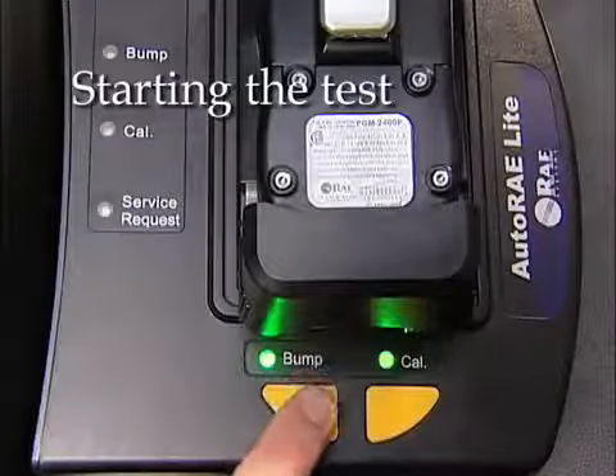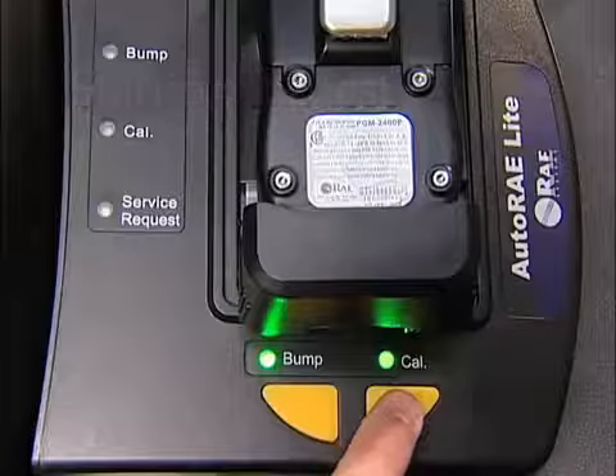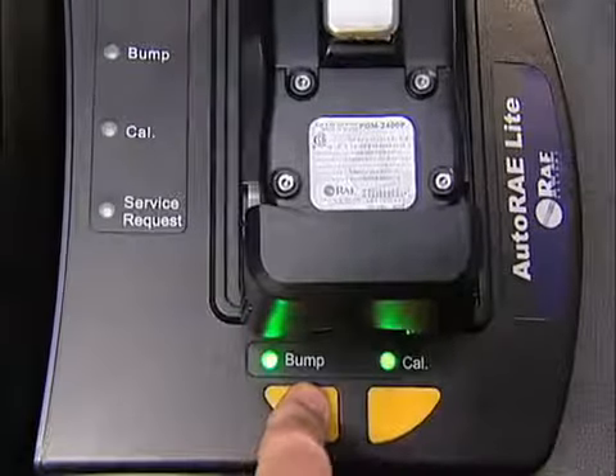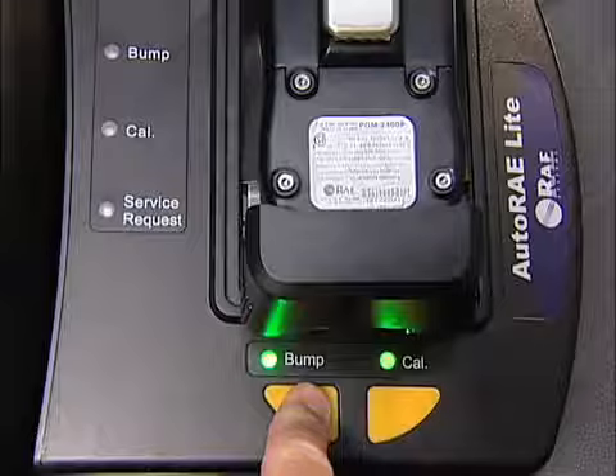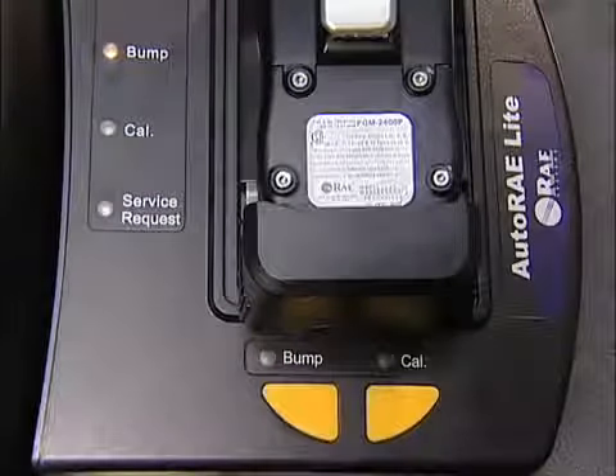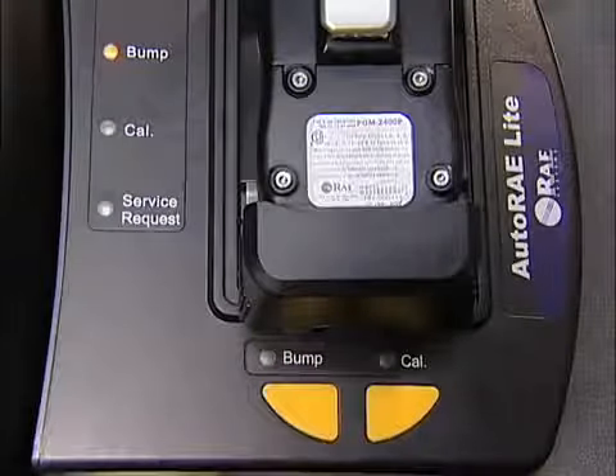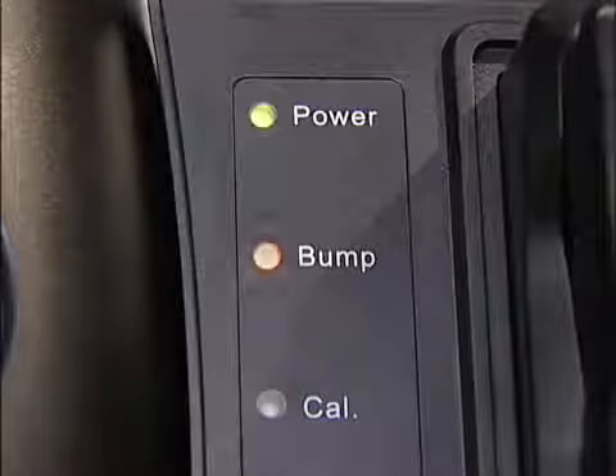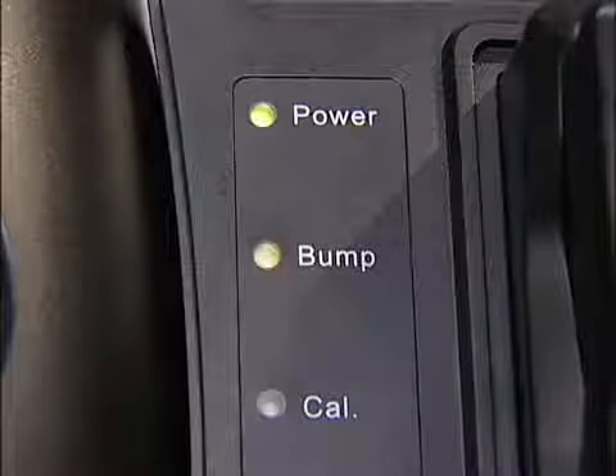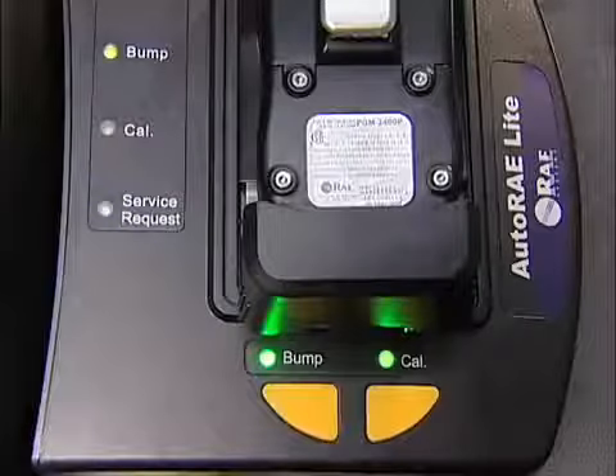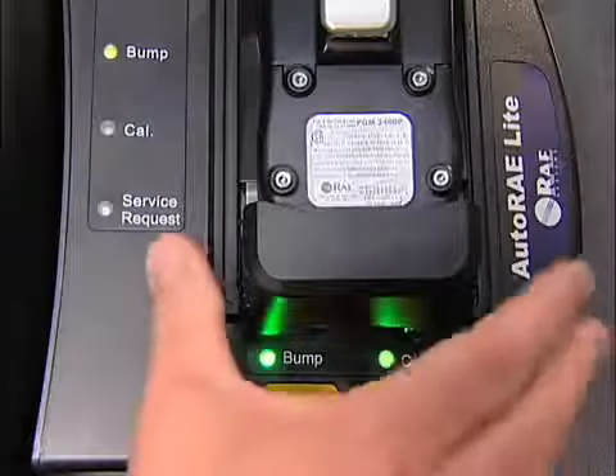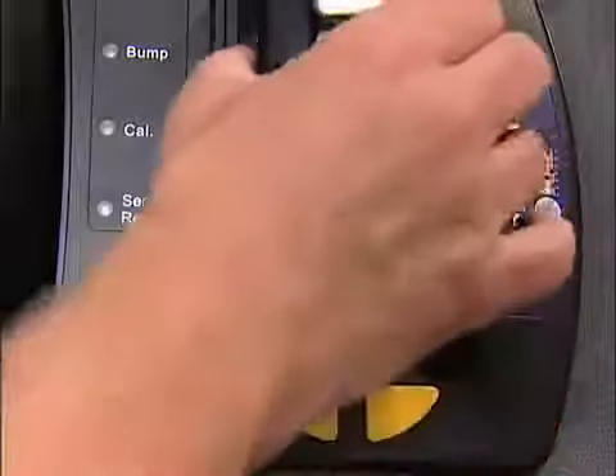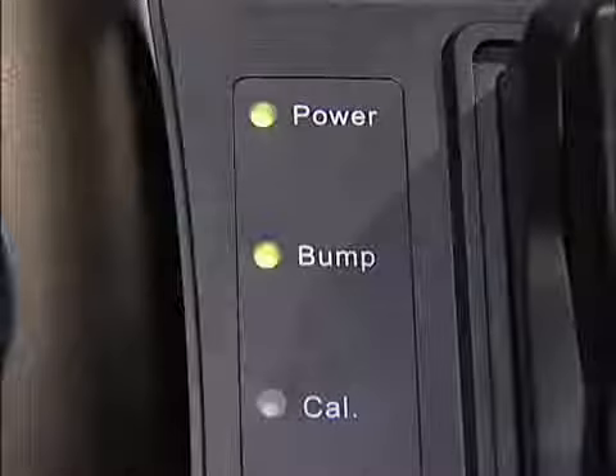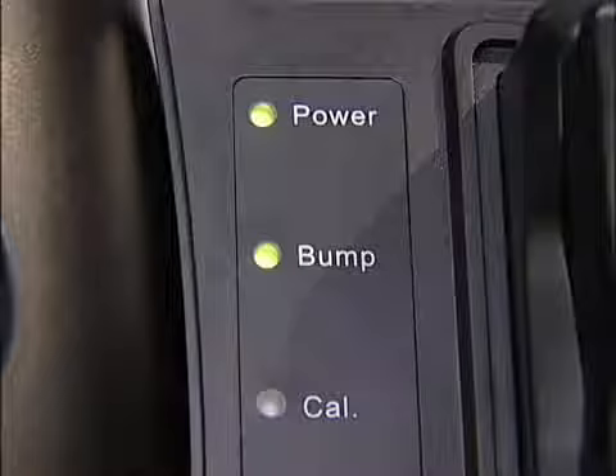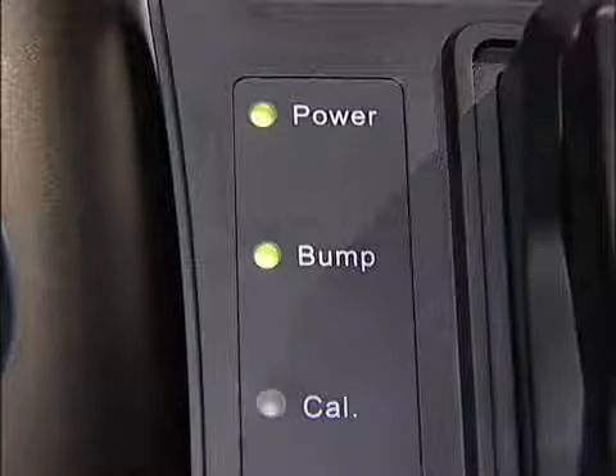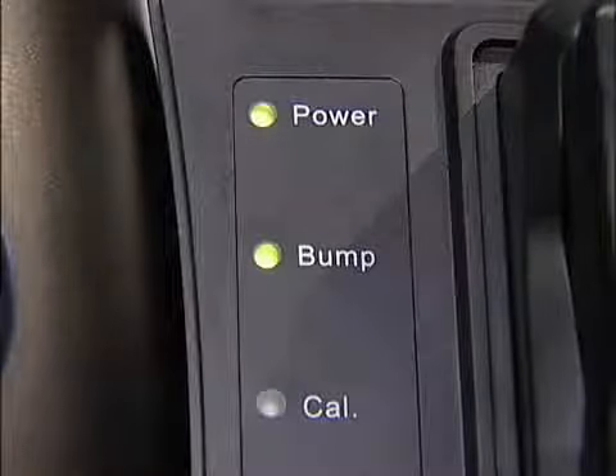Press bump to perform a bump test or press cal to perform a calibration. During a bump test or calibration, the LED above the buttons turns off and the bump status or cal status LED blinks and is orange in color. You will be alerted when the bump test or calibration is complete. When the 2 indicator LEDs above the buttons glow green, remove the QRAE II from the dock. A green LED indicates the bump test or calibration was successful. A red LED indicates the bump test or calibration failed.